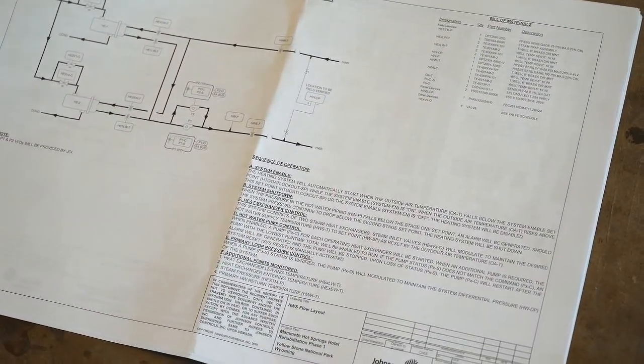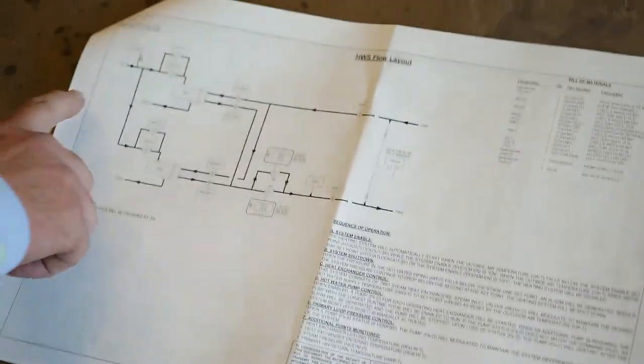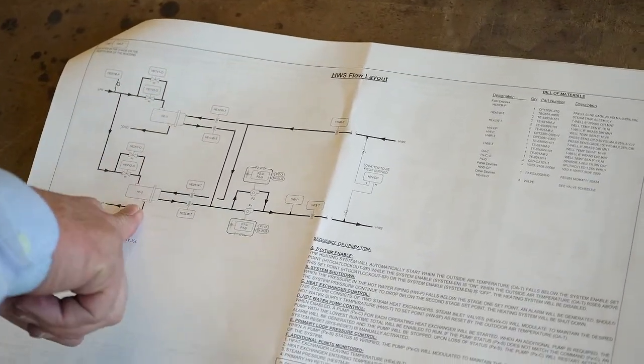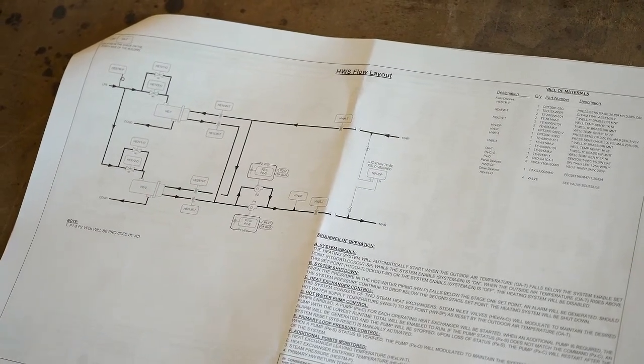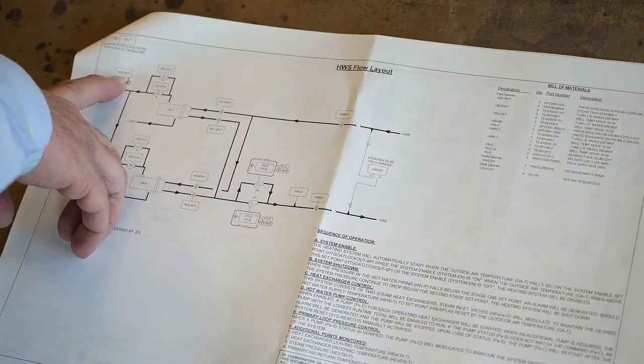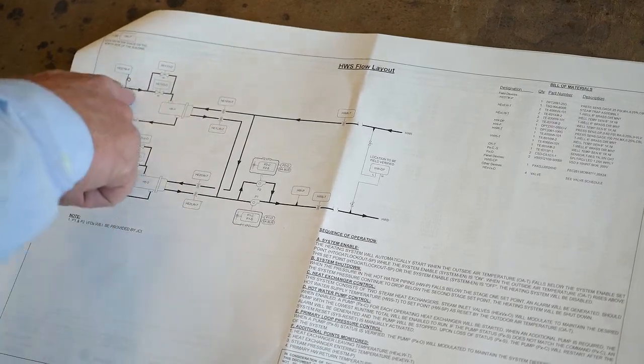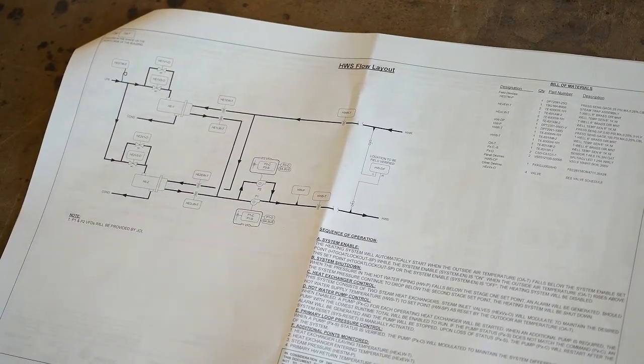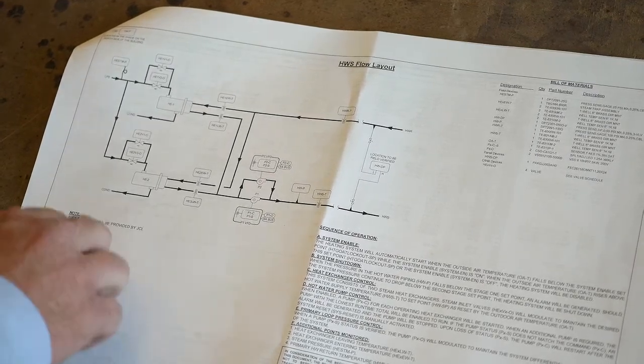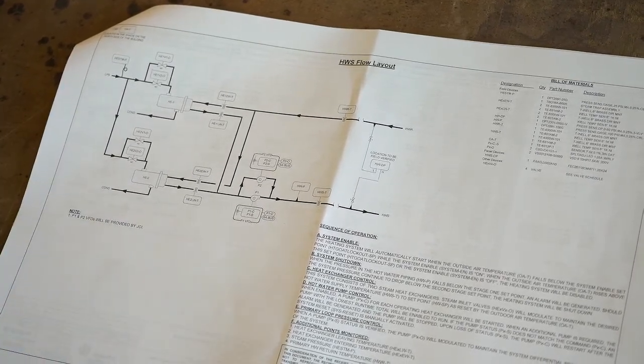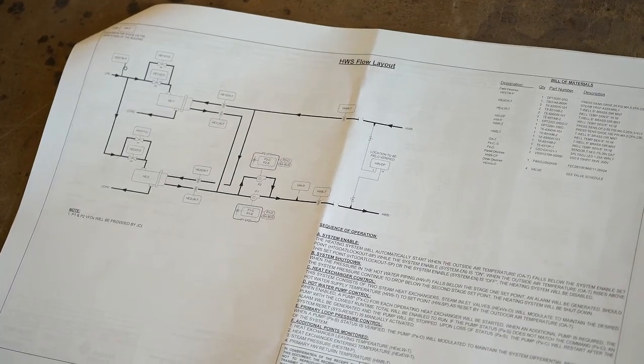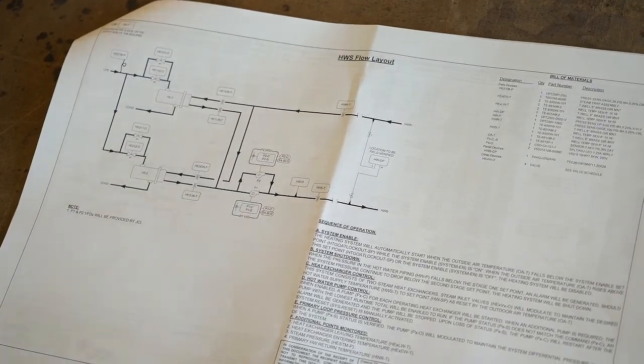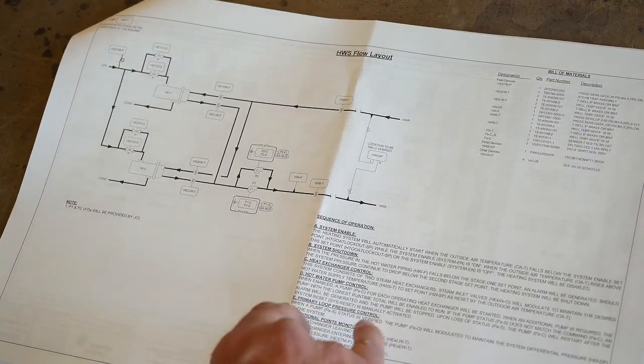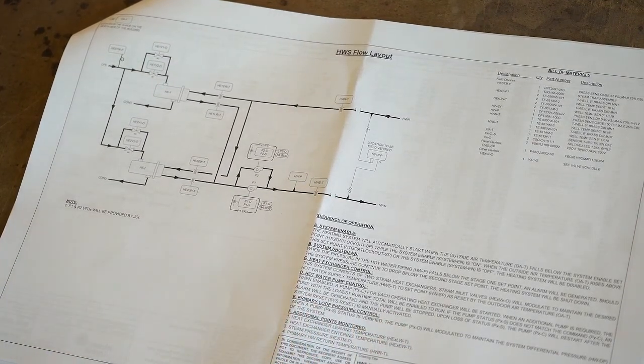So then we'll go to the next page, and this just happens to be the hot water supply flow layout down in the basement. So coming in on this side, we have the steam going to the two heat exchangers. You have dual heat exchangers downstairs. So we have a steam pressure sensor here that we can use to measure the steam pressure. If that steam pressure gets too low, it generates an alarm. Okay. Then what is that steam pressure best at? Between 4 and 8? I believe I have them set at 3 and 6. Okay.